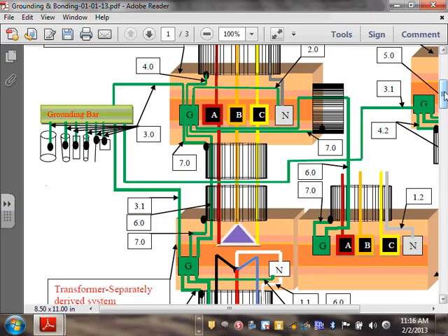Say you have a service coming to your building, guys, and Xcel is giving you 4 conductors, 3-phase and neutral, and there was a storm, if it's coming overhead, or accidentally the lugs on the neutral got loose and you lost your neutral. Now you're pulling three-phase conductors inside your building without a neutral, and your neutral is not grounded. You get into what we call a floating neutral, right?